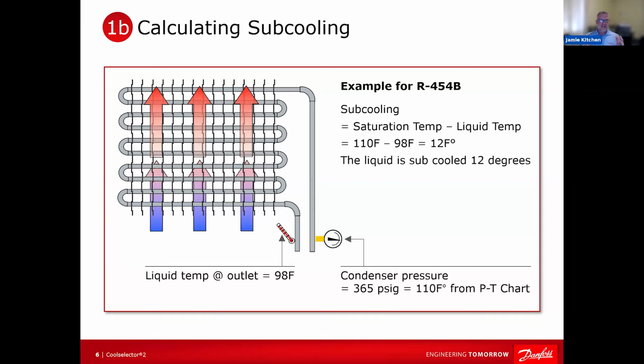So when it goes into the condenser, the first thing it does is, I don't know, what do we call it? De-superheat. It cools down sensibly. I'm going to use the word de-superheat. I just created it. So it's going to de-superheat, and the temperature is going to drop. And it's going to drop to the point where, if you cool it down any more, it's got all this pressure pushing against it, and it hasn't got enough energy to stay a vapor. So the pressure starts to push it together and it starts to form a liquid.